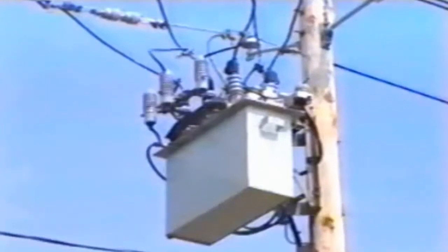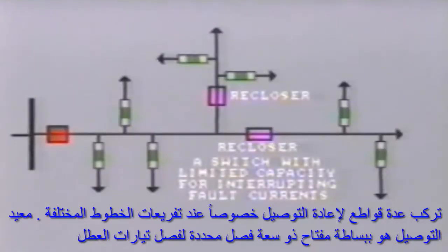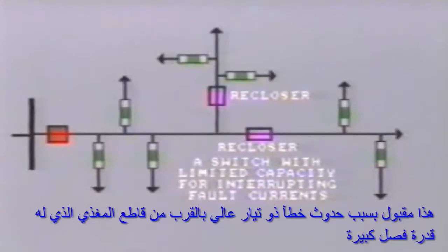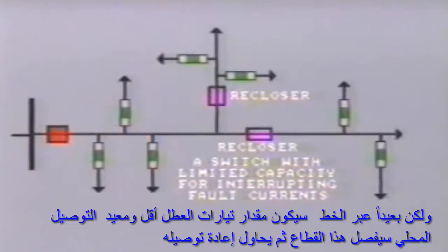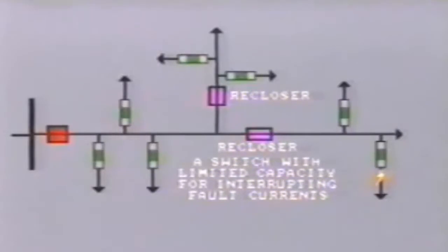On distribution systems, another more direct reclosing arrangement is often used in addition to the reclosing relays that we've been talking about. The device in question is known as a recloser, and it is usually installed in the line itself at some remote distance from the feeder breaker. Several reclosers may be installed, particularly at points where different sections are tapped off. The recloser is essentially a switch with limited capacity for interrupting fault currents. This is acceptable because very high levels of fault current occur closer to the feeder breaker, which has greater interrupting capacity. However, further down the line, fault currents are less, and the local recloser will clear that section of line and then attempt to reclose.